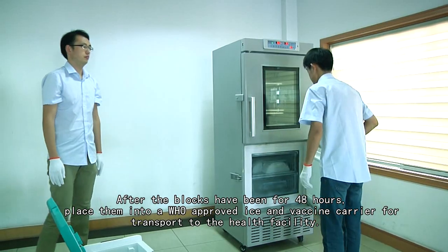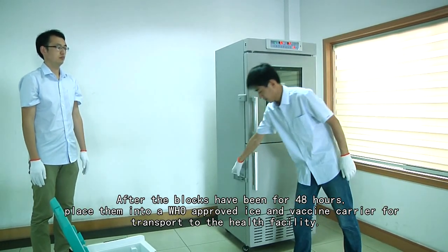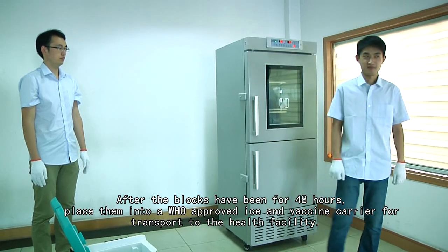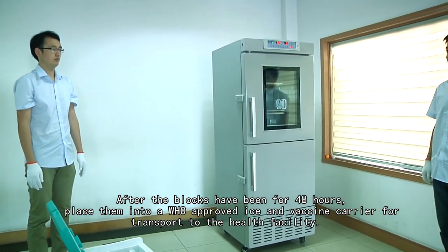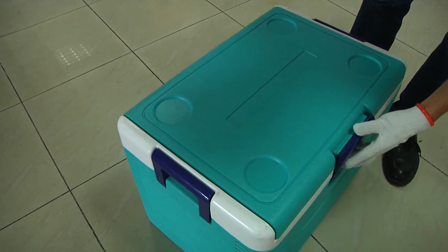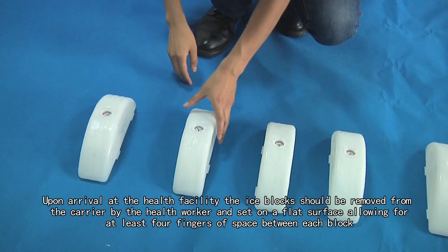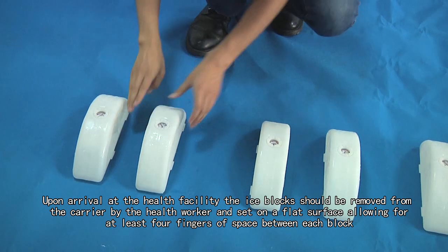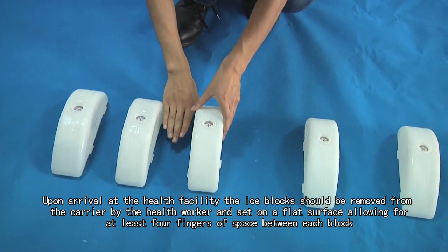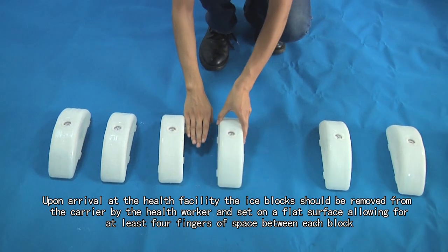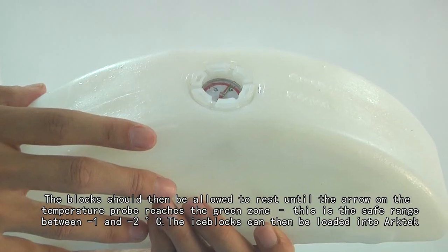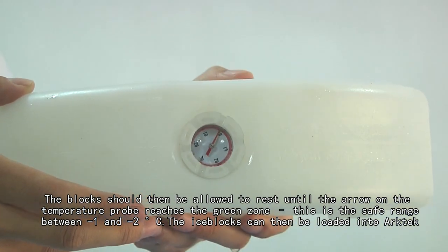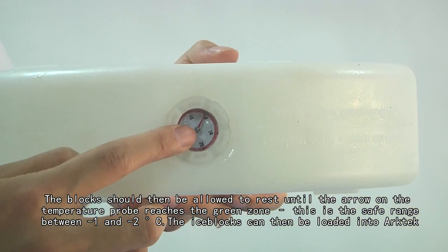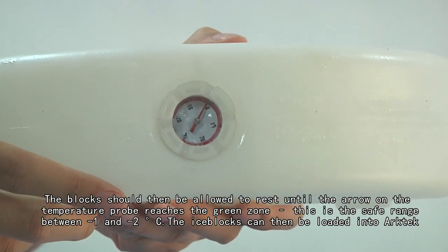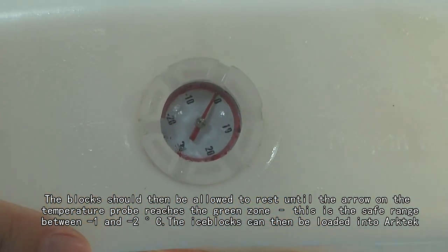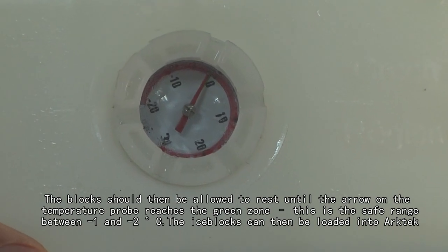After the blocks have been frozen for 48 hours, place them into a WHO-approved ice and vaccine carrier for transport to the health facility. Upon arrival at the health facility, the ice block should be removed from the carrier by the health worker and set on a flat surface with at least 4 fingers of space between each block. The block should then be allowed to rest until the arrow on the temperature probe reaches the green zone. This is the safe range between -1 and -2 degrees Celsius. The ice blocks can then be loaded into the Arktek.